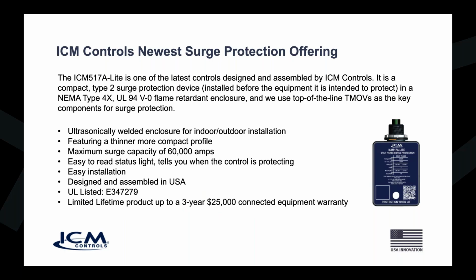enclosure. The plastic is UL94 V0 flame retardant, and we have top-of-the-line thermally protected metal oxide varistors, TMOVs, inside there, which are the key elements for surge protection. The structure is ultrasonically welded, so you can be sure it's good for outdoor or indoor installation. A thinner, more compact profile makes it easier to install in tight spaces. Maximum surge capacity of 60,000 amps for a single hit, and many more hits under 60,000.